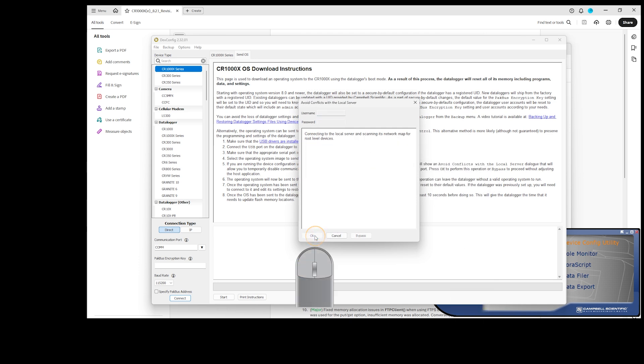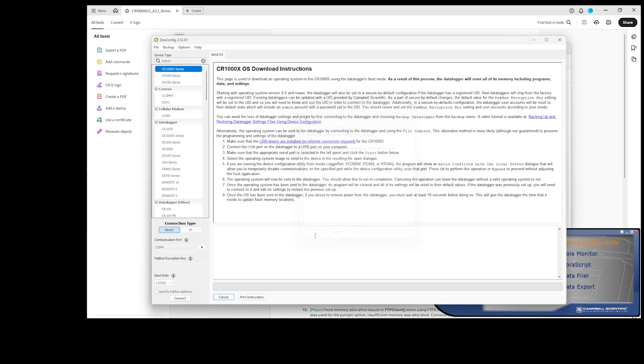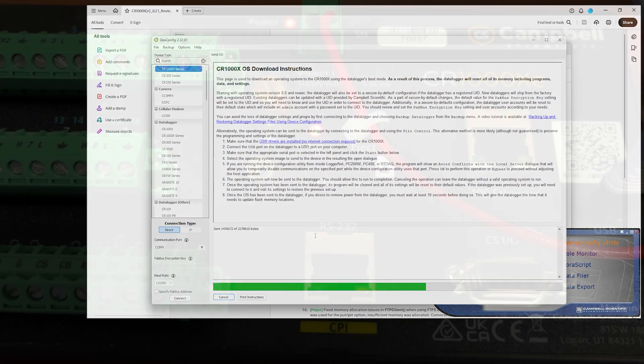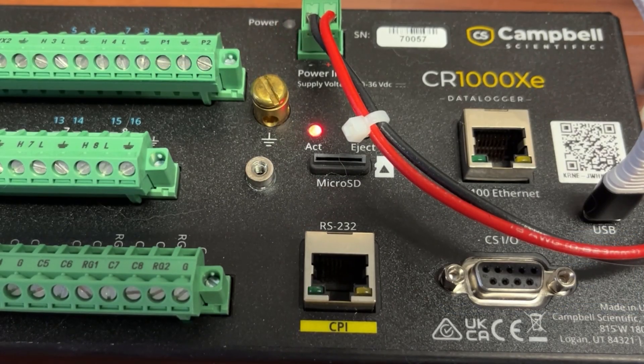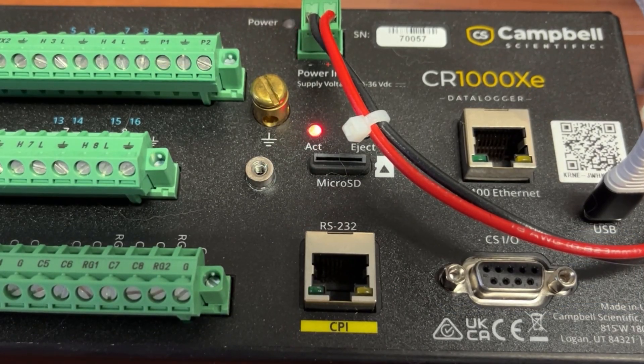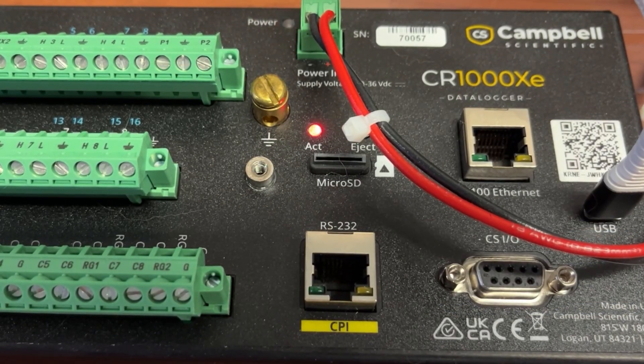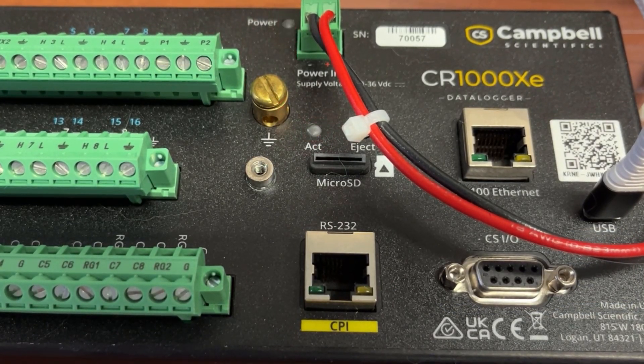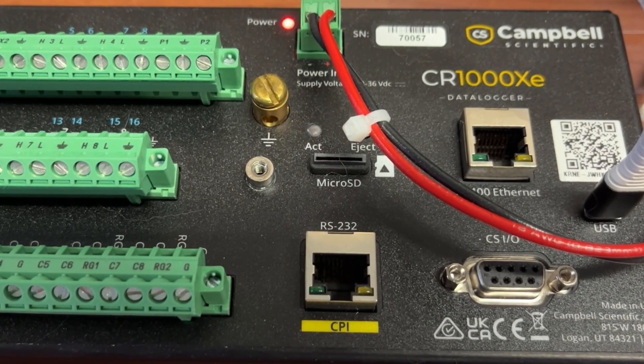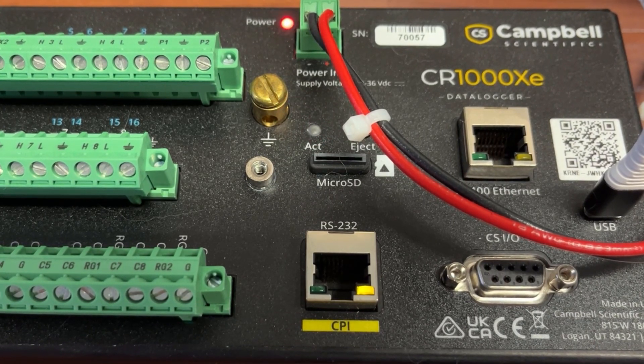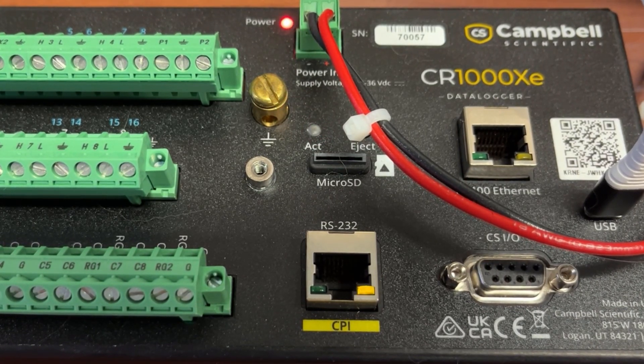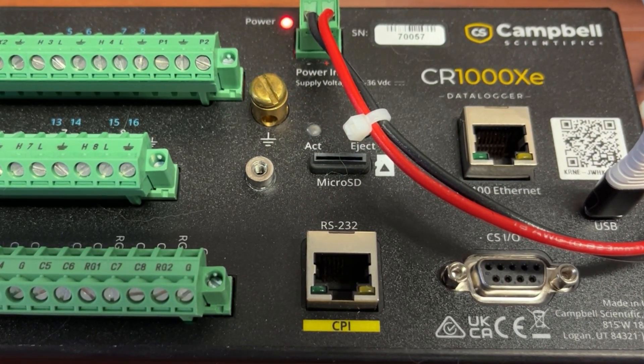Click OK when a window pops up about avoiding conflicts with the local server. This is where older CRBasic data loggers would get powered back up to send a sync byte to the Device Configuration Utility. The time it takes to send the OS has been sped up for this demonstration. It will take a few minutes for the data logger to configure the operating system. While this is happening, the activity and power LEDs will flash. Wait until the activity LED stops blinking and the power LED is on solid before proceeding.